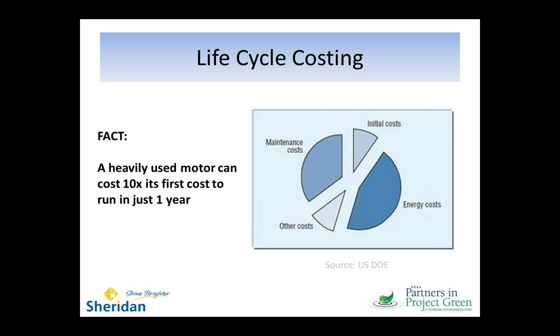The facts are that motors tend to cost more to operate over their lifetime than their first cost, and you can see from the graph here that the initial costs are a small piece of this entire wedge of energy costs, other costs, maintenance costs. And I put a little factoid on the side that a heavily used motor might use 10 times as much of its first cost to run in just the first year. And in general, the statistic we might see thrown around in the industry is that 20% of the overall life cycle cost of a motor is in the first cost. So 80% you could attribute to operating the motor.